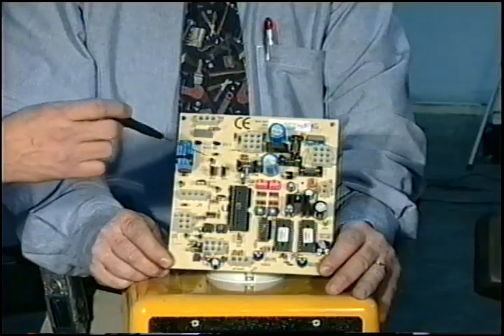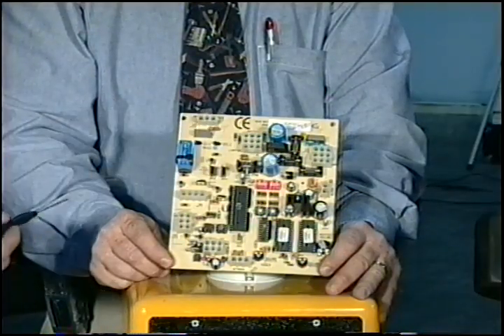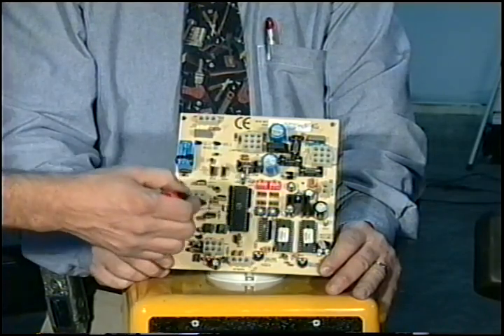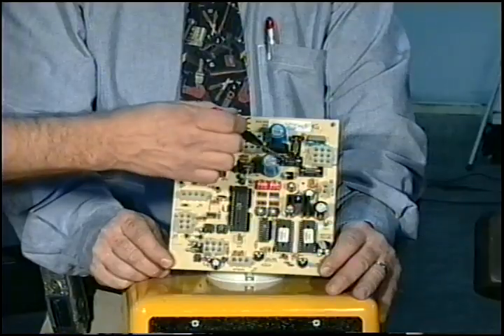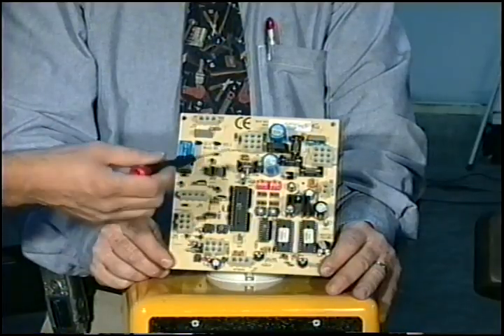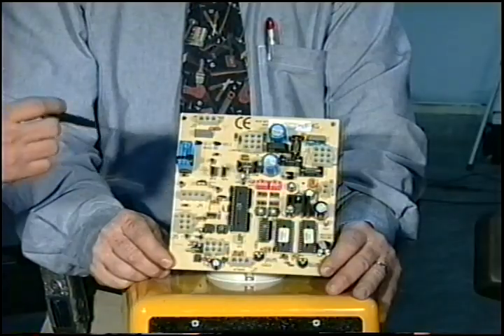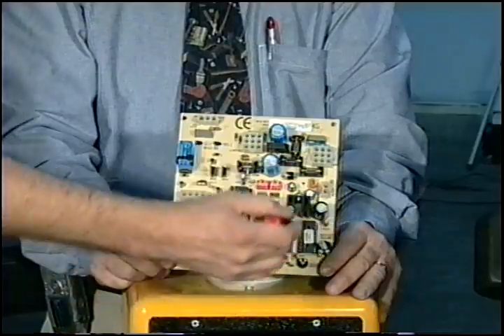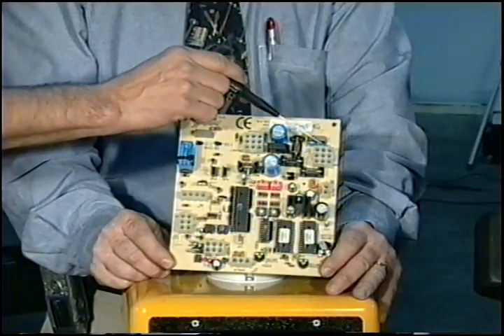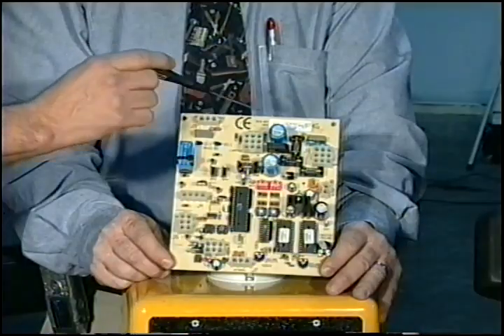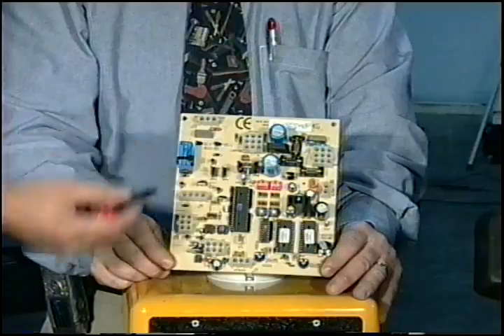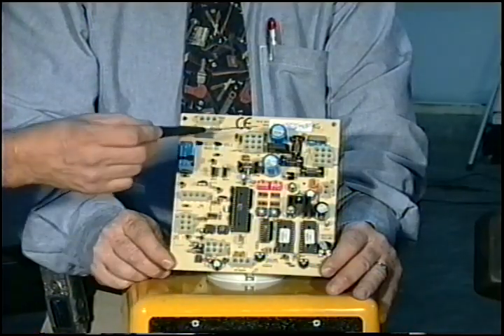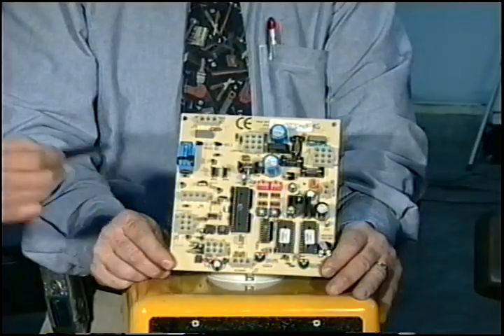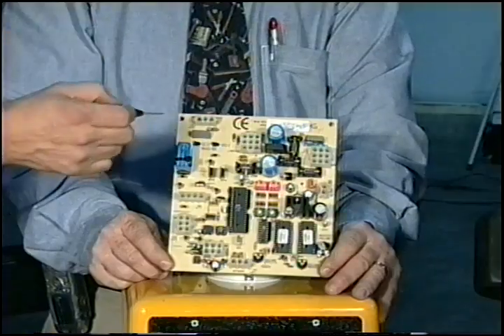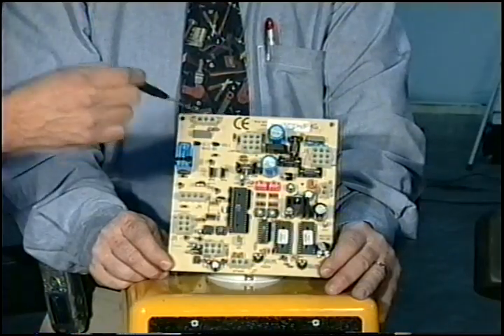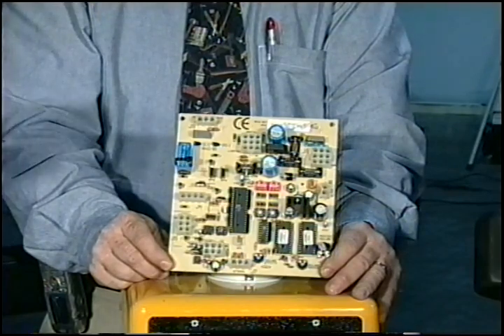The one this way is for your 24 volts. If you're blowing this one, what I usually tell people, it could be that you have a catastrophic short on your board causing the fuse to blow on your 24 volt circuit, or it could be something external. Best way to see if it's something external is unhook all your connectors except for J1, because J1 is your power going into the board. Okay, you plug in J1, fuse doesn't blow, board most likely is fine. Then what you do is you plug in 1 connector at a time until the fuse blows. When it blows, then you want to look at your connector diagram sheet, find out what that connector's for, and usually you can find your problem that way.